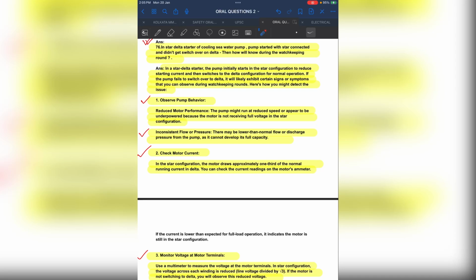So first of all, why are you using the star connection? To reduce the starting current, because when you start a motor with a pump coupling, it will take high current. If you directly start a motor with a pump connection, it will take a very high current, approximately 5 to 10 times, like a direct-on-line starter. But in star delta, we reduce the current to 1/3 of the delta current, because the motor runs in delta at 440, and in star connection we are giving the reduced voltage. It means the voltage is reduced in the star configuration, so our starting current will also reduce.